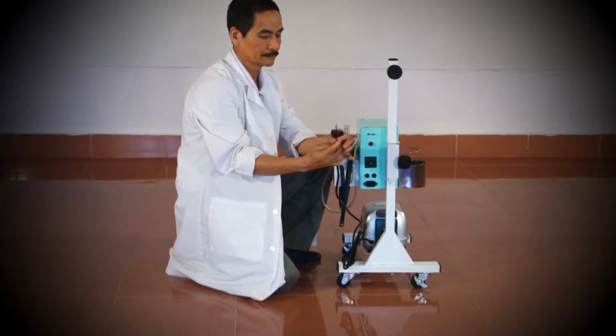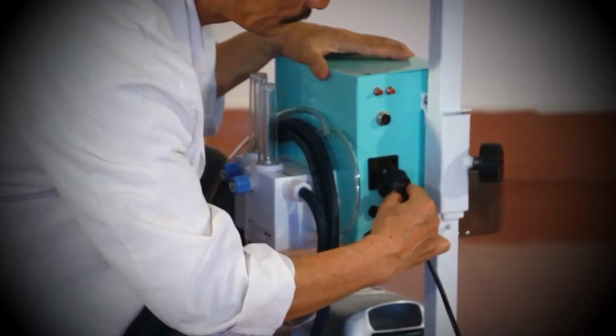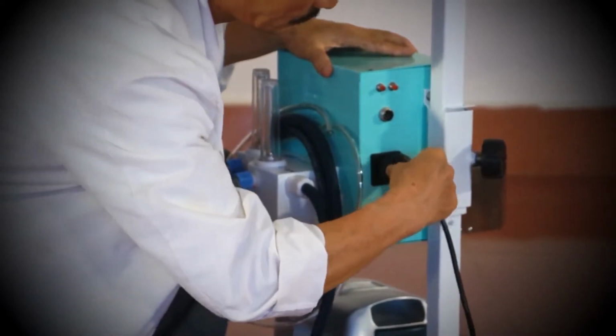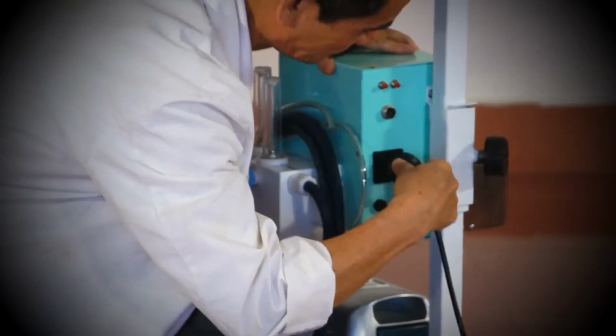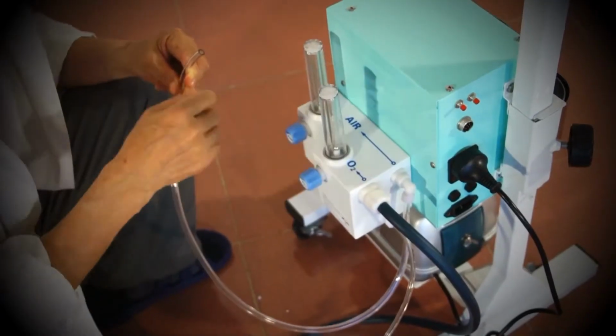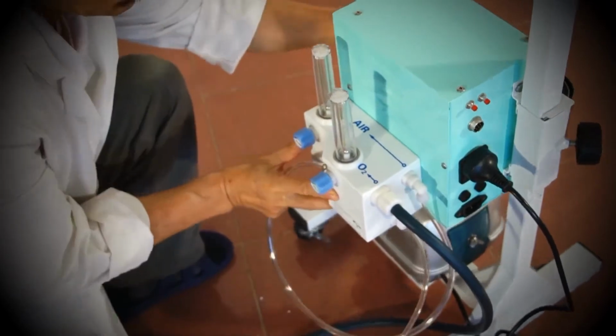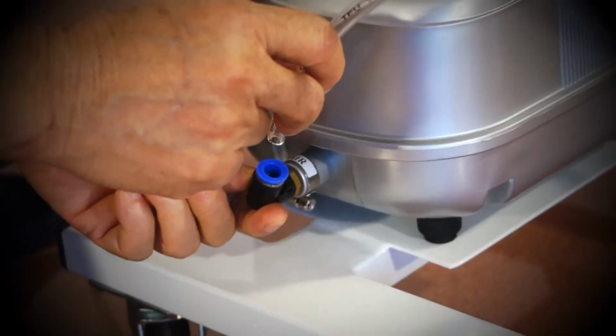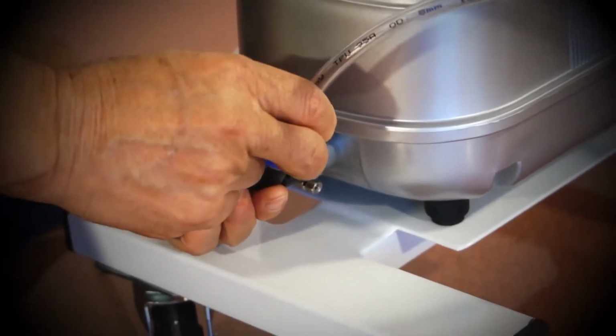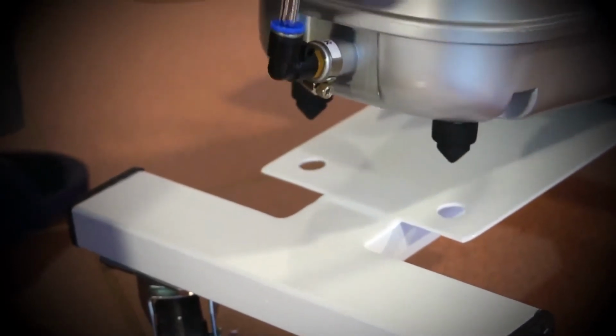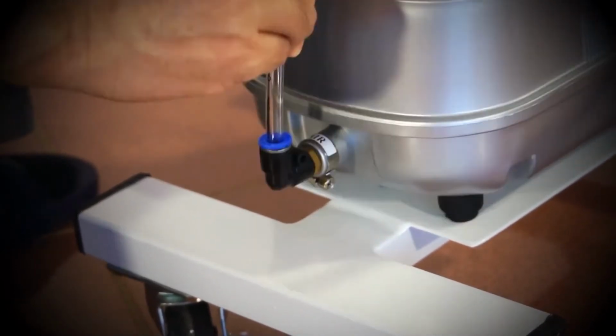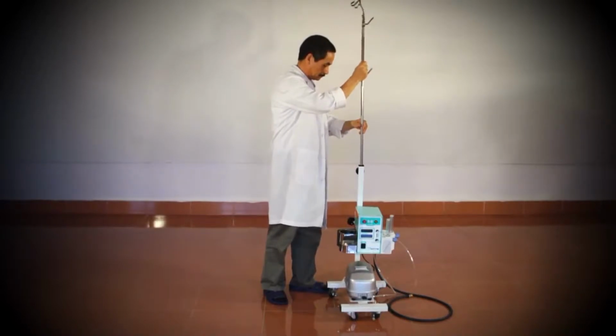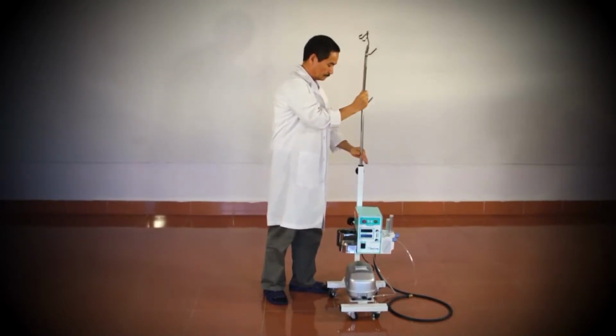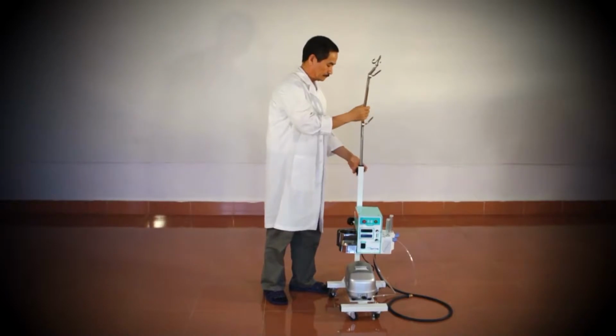Once the air compressor is back in place, connect the air compressor power cord to the socket on the control box. Then connect the air tube from the CPAP main unit to the air compressor. Pull gently on the air tube to ensure that it is firmly secured. Next, insert the CPAP arm into the main unit and secure it by tightening the black knob.